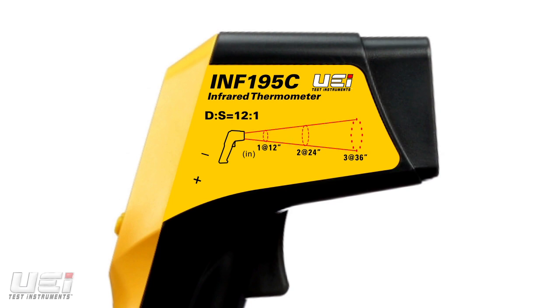This is the distance from an object in relationship to the size of the spot being measured. For example, from 12 inches away, the measured spot is 1 inch. From 24 inches, the spot is 2 inches, and so on.